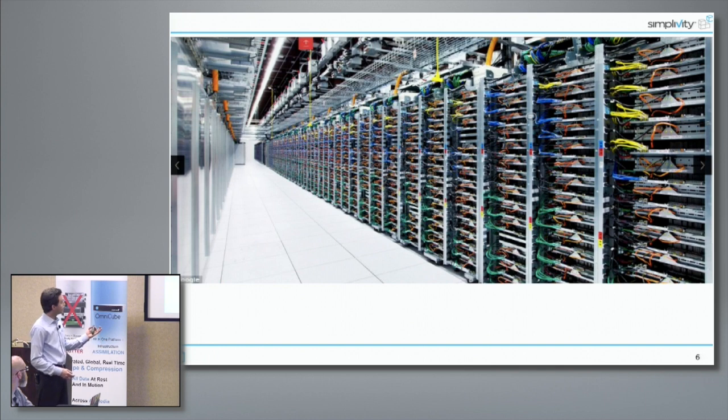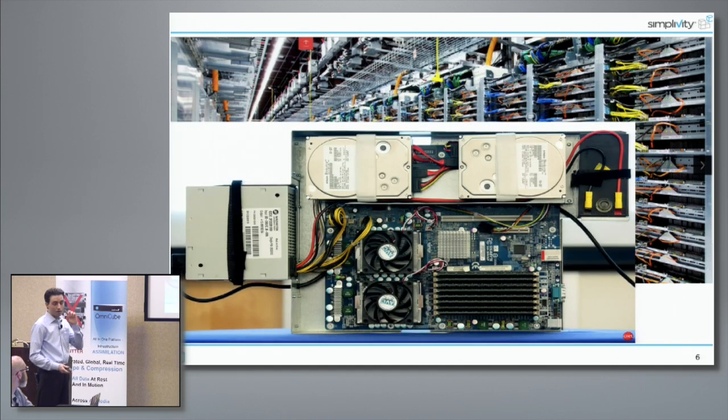Maybe it looks more like these systems. So we drill down and look at those. Folks may know this is actually a picture of a previous gen Google server. So the favorite part of this for me is that both the hard drives and the power supply and the battery that hangs off the other end of the system are all held in place with Velcro. And there's no redundancy for the power supply, which in most cases is one of the most common components to fail. So this, I've yet to present to a customer who says that this is what any of their infrastructure looks like. But this is really the basis for these giant scale-out environments.